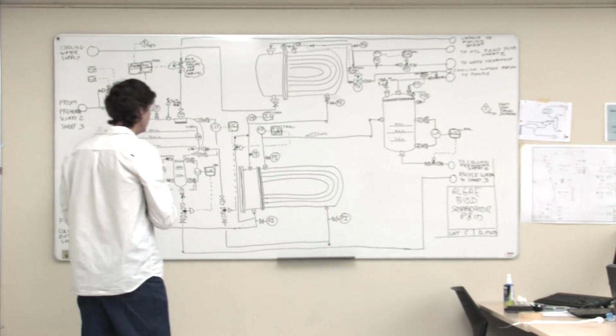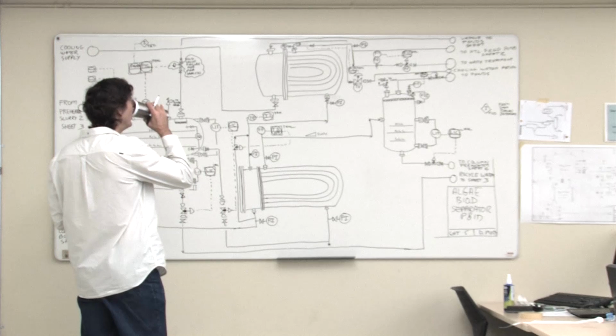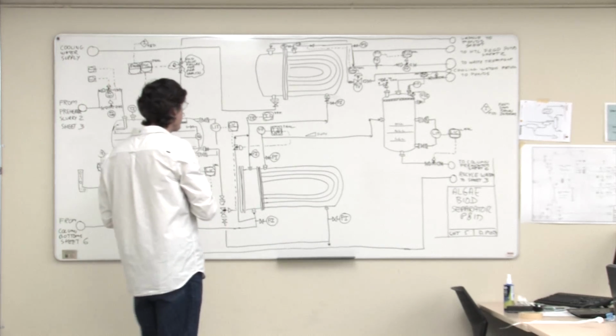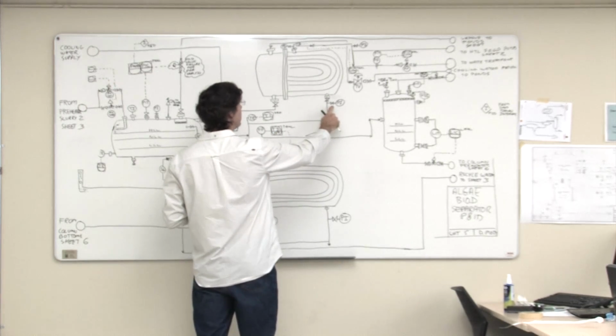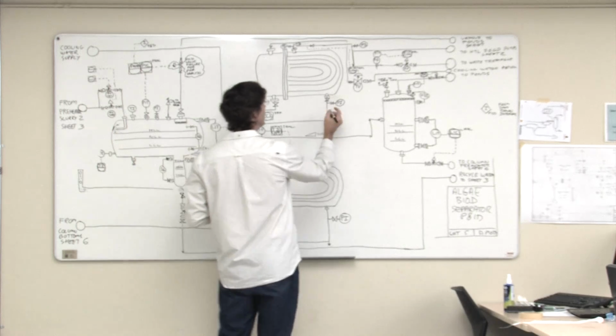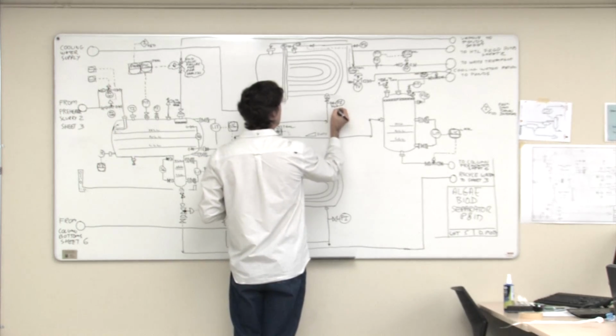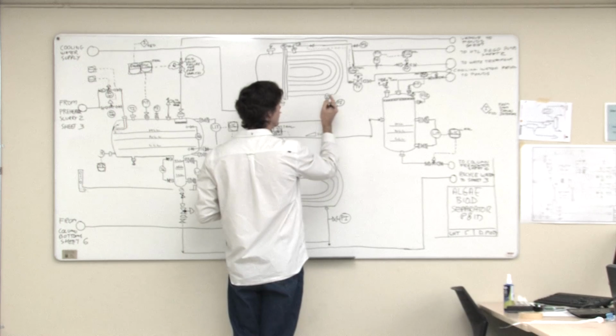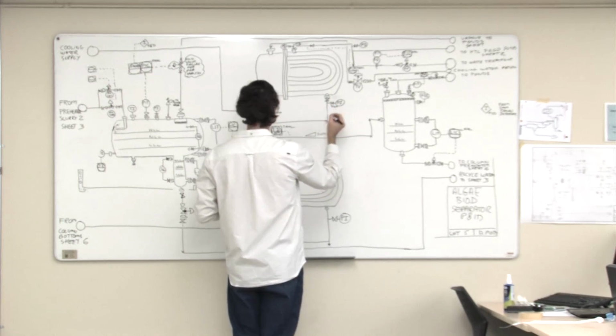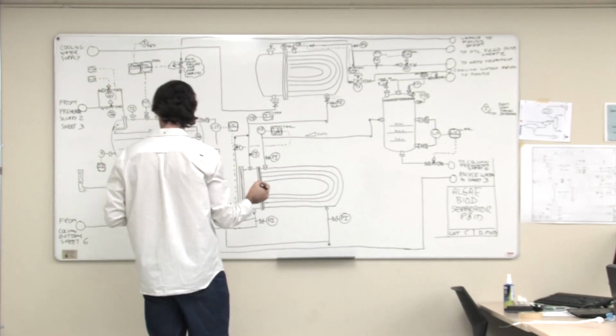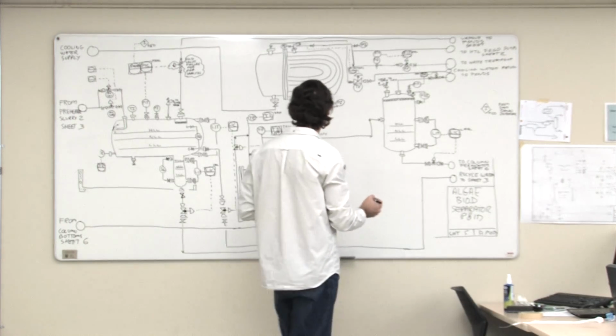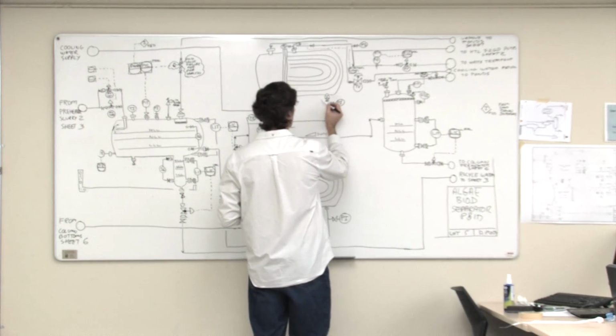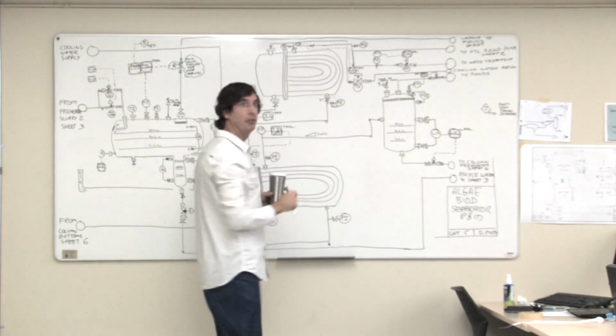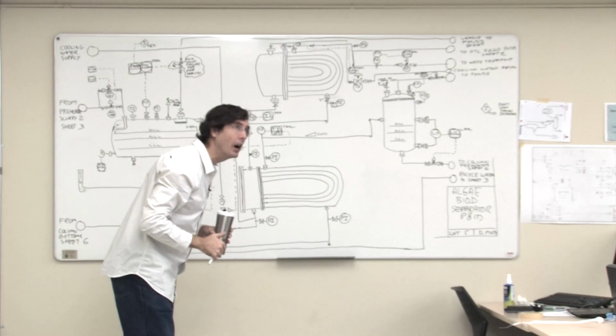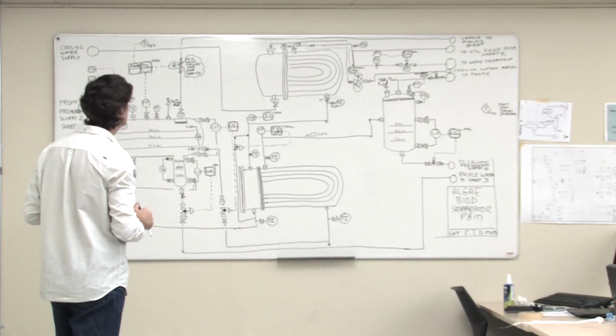An extra nozzle on a heat exchanger is just costing money, where we can stick it on the piping for a lot less money. Do you need that extra isolation valve on the PI, or do you already have the isolation valve coming out of the machine? Here? Yeah, like do you need both of those? Yeah, this is like a 3/4 inch, and this is full line size. So this could be, I don't know what our flow rates are, but this is off the column bottom sheet. We're like 6,000 kgs an hour or something like that. So this is probably, I don't know, 2 inch or 3 inch or something like that. Where that's just a little valve. You can look around this room actually, and you can see some PIs in the chilled water system.